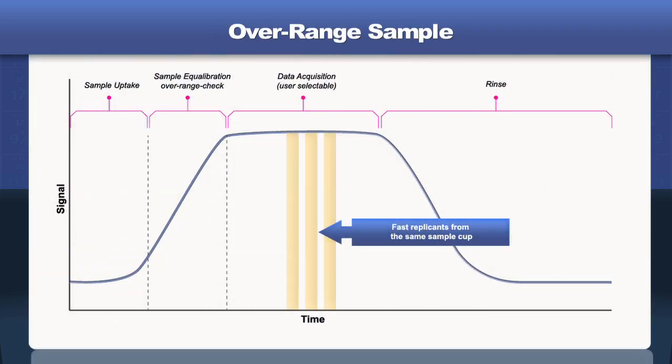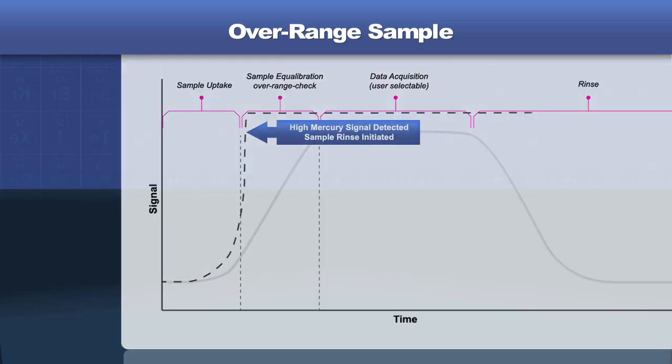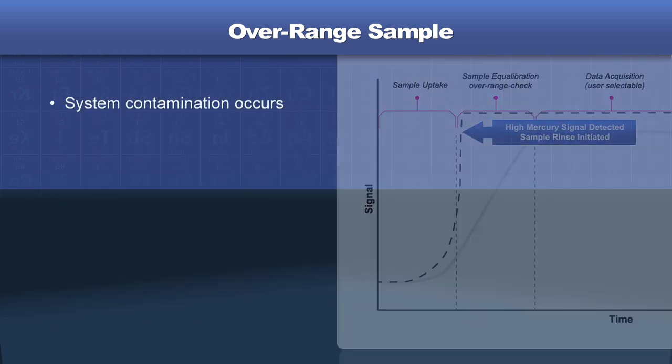On occasion, a sample with unexpectedly high amounts of mercury may be encountered. This can completely contaminate the system, forcing the operator to stop the sequence and clean or repair the system.